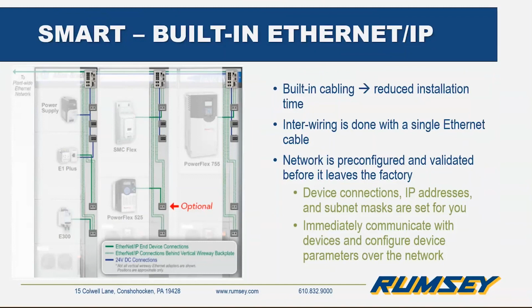So this is kind of an example of what the built-in Ethernet IP network looks like. As you can see, there's an Ethernet cable. I think it's the green cabling on the diagram here. It's connected to each motor control device in each individual unit, and then it's actually wired through the vertical wireway channels to Ethernet switches. With the networked MCC, you can greatly reduce installation and startup time because the cabling, configuration, and validation is all completed before it leaves the factory.